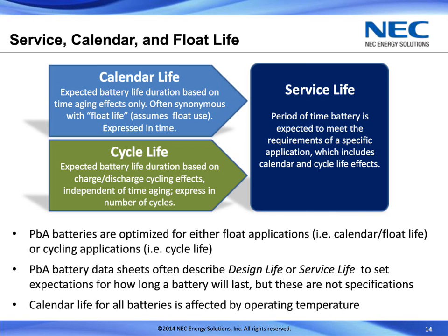A lot of data sheets for many batteries will talk about a design life or service life. These aren't necessarily super technical terms because they have to assume something about what the application is to figure out how the combination of calendar and cycle life actually provide the longevity of that battery. The other thing to note is that all batteries, independent of the technology, are affected by the operating temperature and ambient environments of the battery, and that has an effect both on the calendar life and the cycle life.